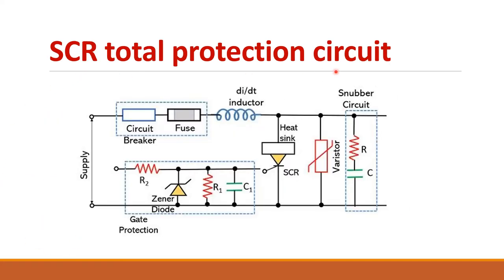This is the complete SCR protection circuit. Here is the SCR. To maintain temperature, a heat sink is used — the SCR is placed on the heat sink so that generated heat is dissipated. A varistor is used for overvoltage protection, and a circuit breaker and fuse are used for overcurrent protection. The inductor is for limiting dI/dt and the snubber circuit is for dV/dt protection.